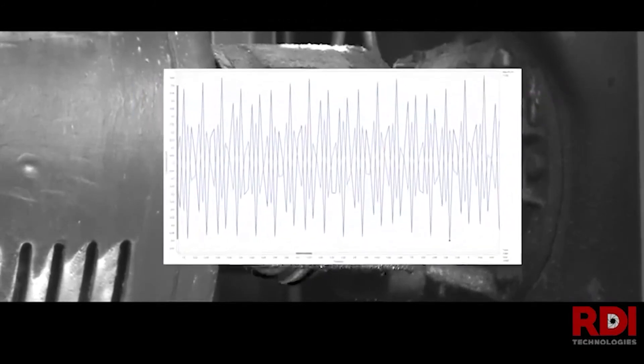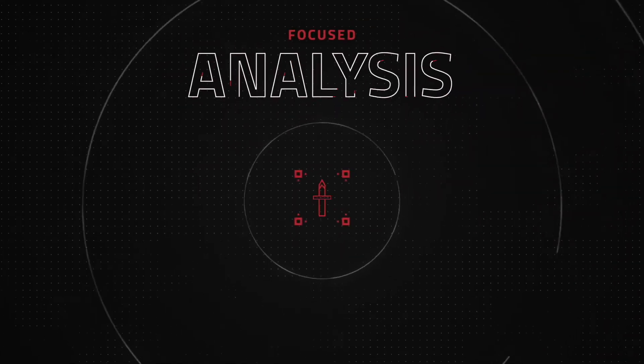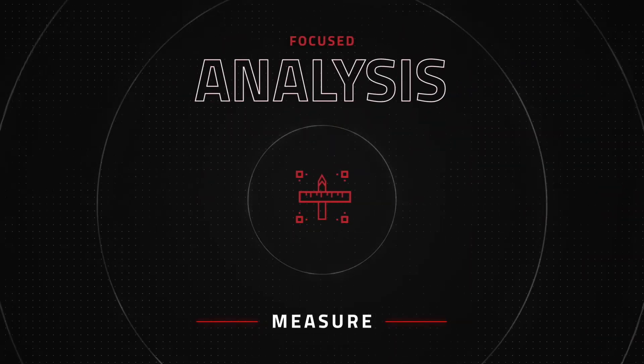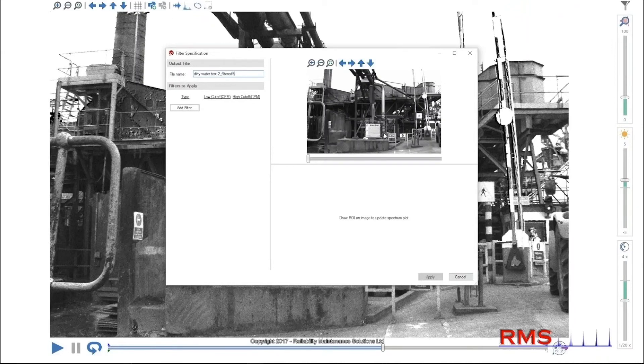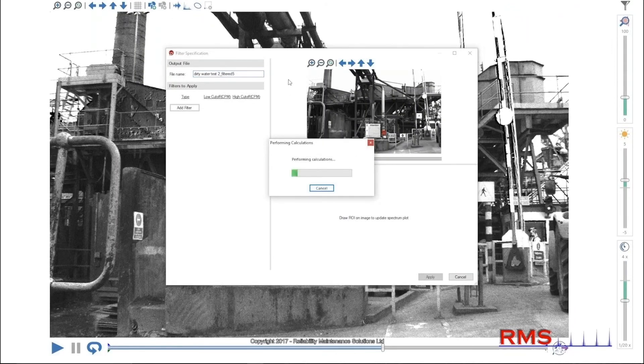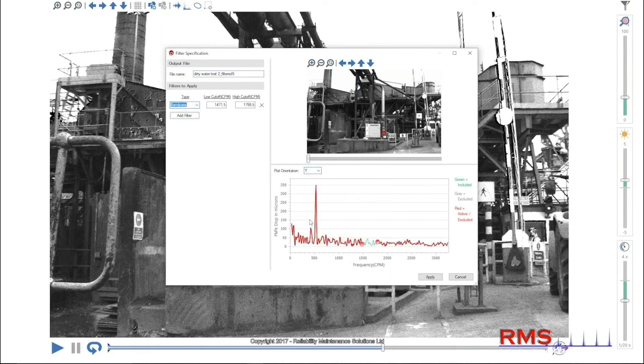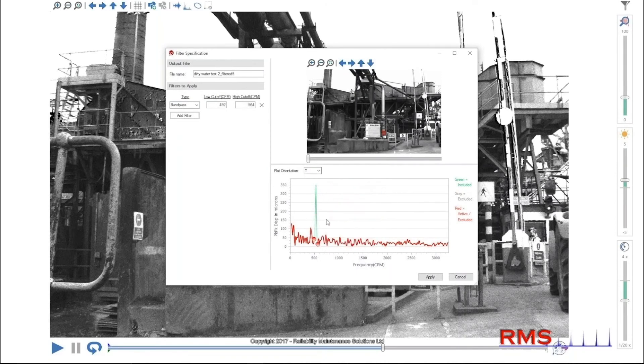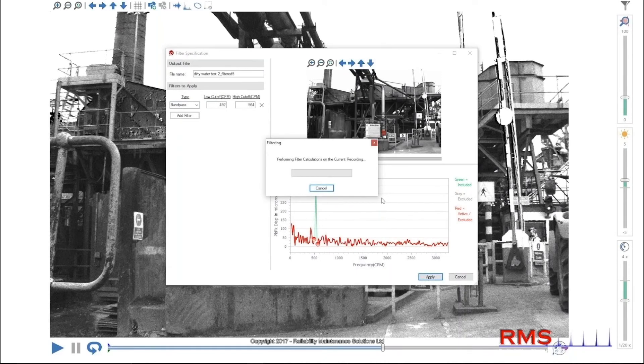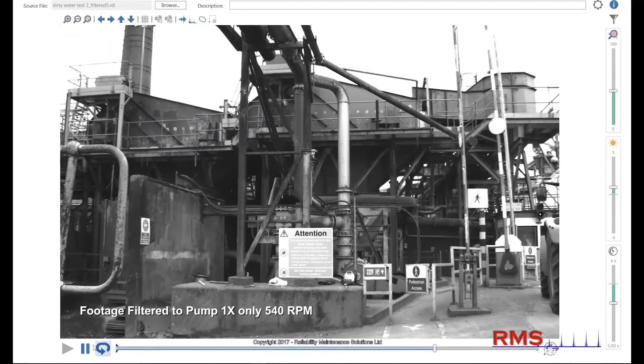Motion amplification is far beyond just visualization and has many advanced analysis features. If you're interested in how a single frequency or frequency range is affecting your asset, you can filter for individual frequencies or combinations of frequencies by using band pass filters, band stop filters, and thresholds to pinpoint and accurately visualize your data. Any combination of filters is possible. As you can see in this example, the customer was able to filter for one times the pump to see how the vibration of the pump was causing motion throughout the piping.